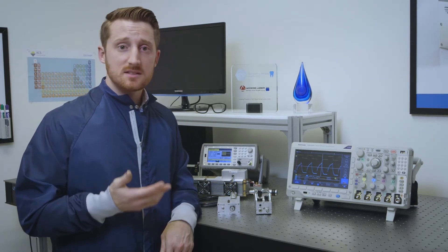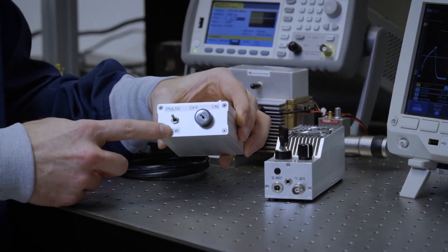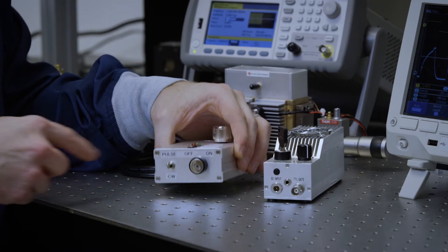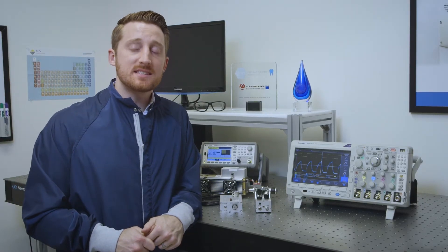This can be done simply through the LC3 controller of changing from CW to pulse after making the appropriate adjustment of your DC power supply.